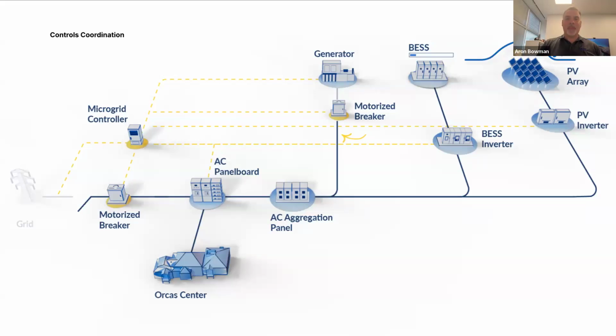That goes too with controlling the PV array. In an off-grid situation, we can also generate power with the PV, but our controller tells the PV the power output it needs to put out. So we'll curtail that PV to match the load and match the ability to charge the batteries as well. There's a lot of integration.